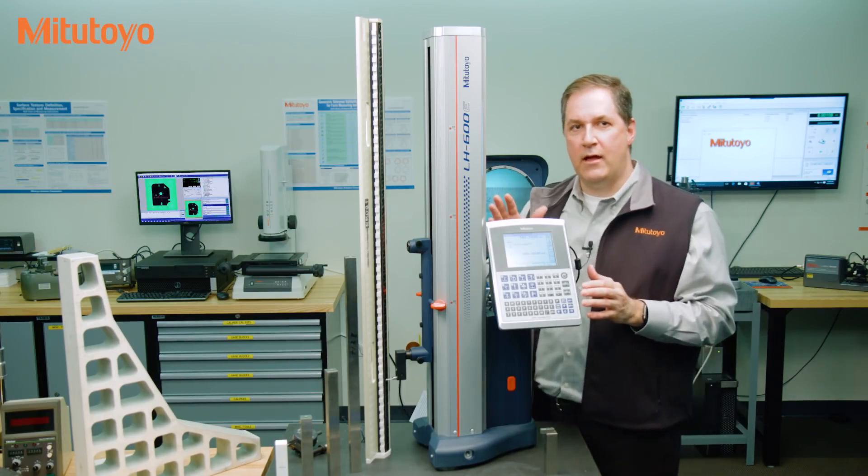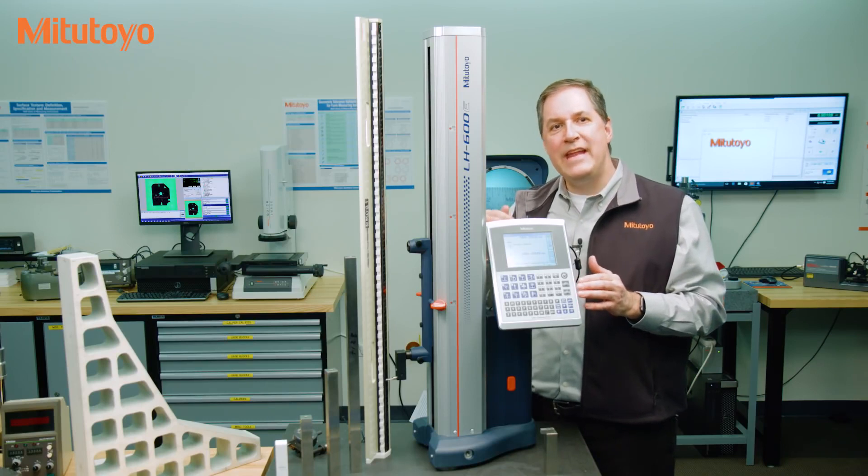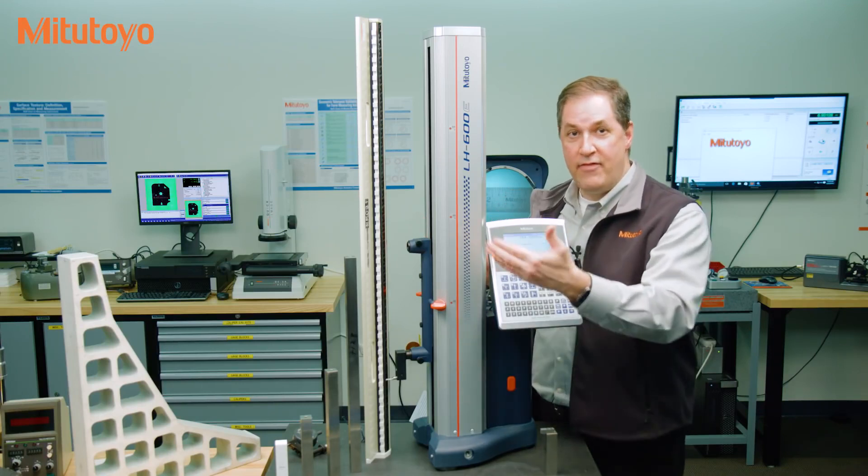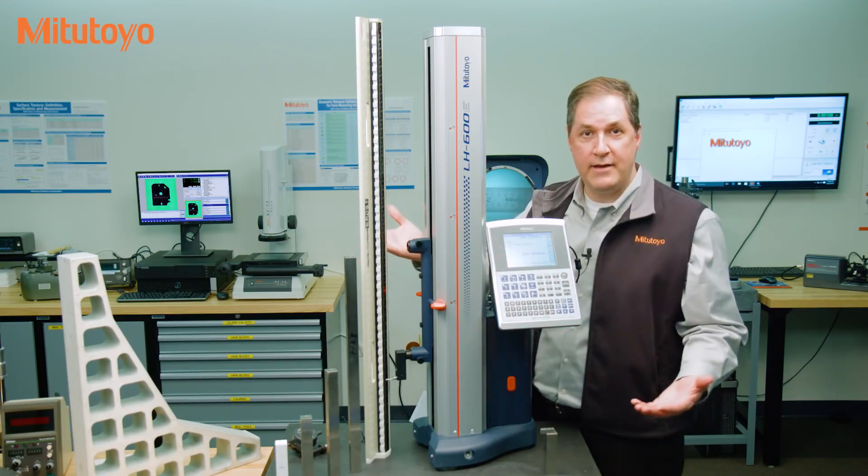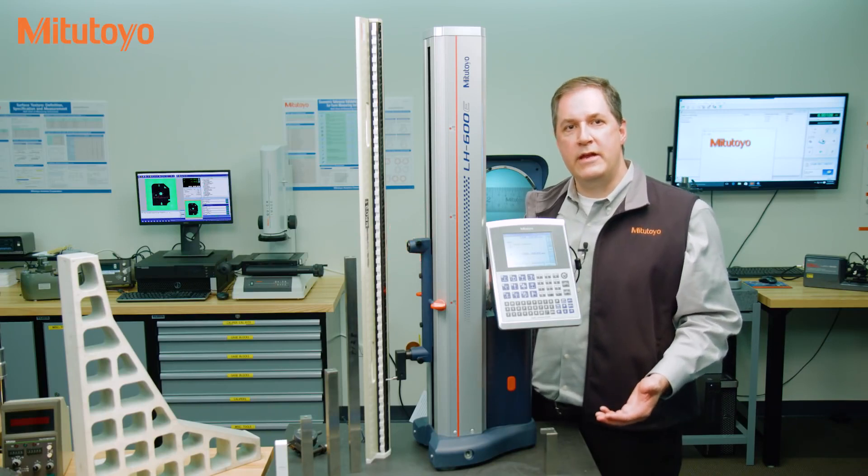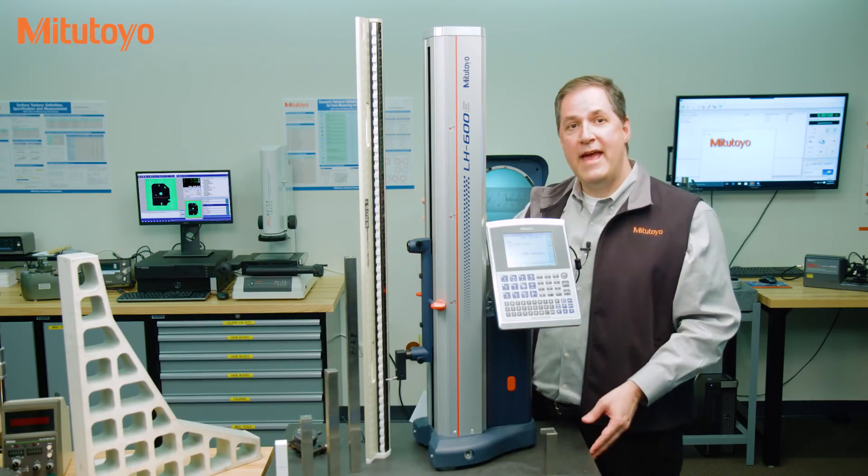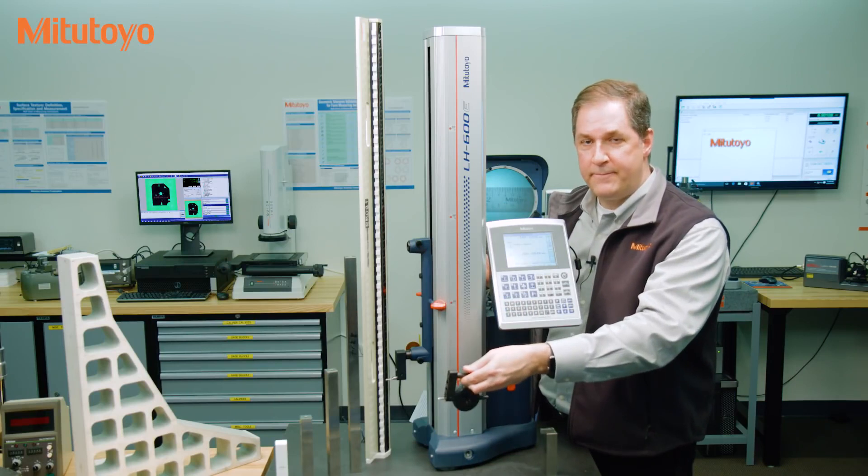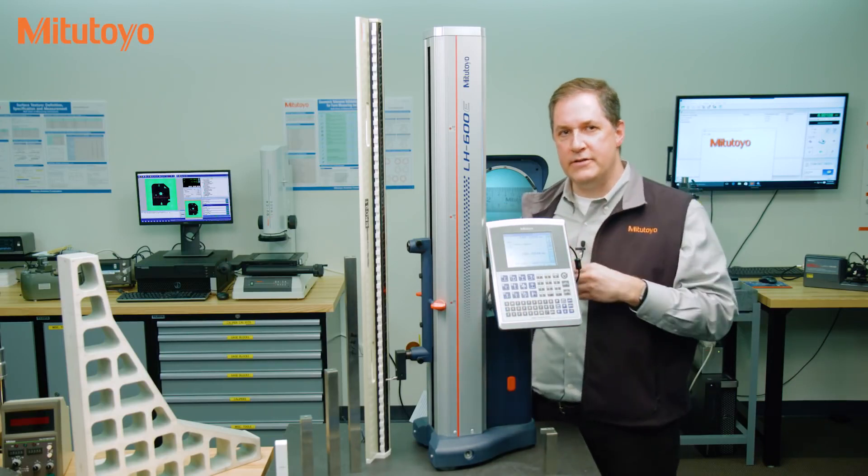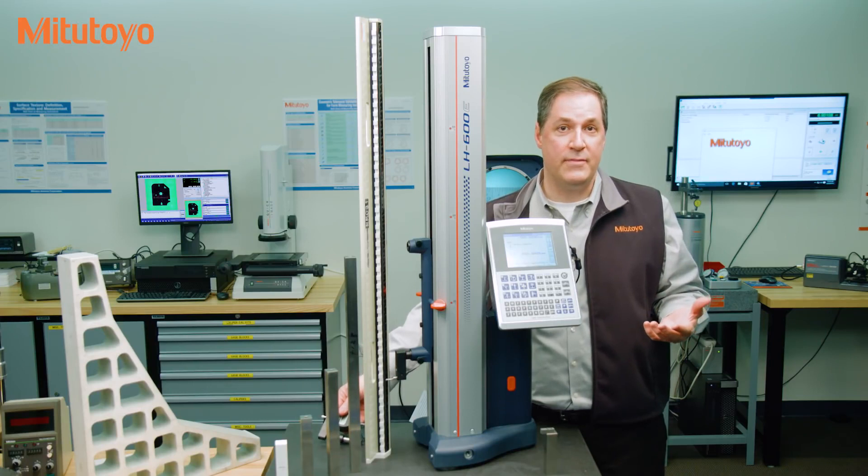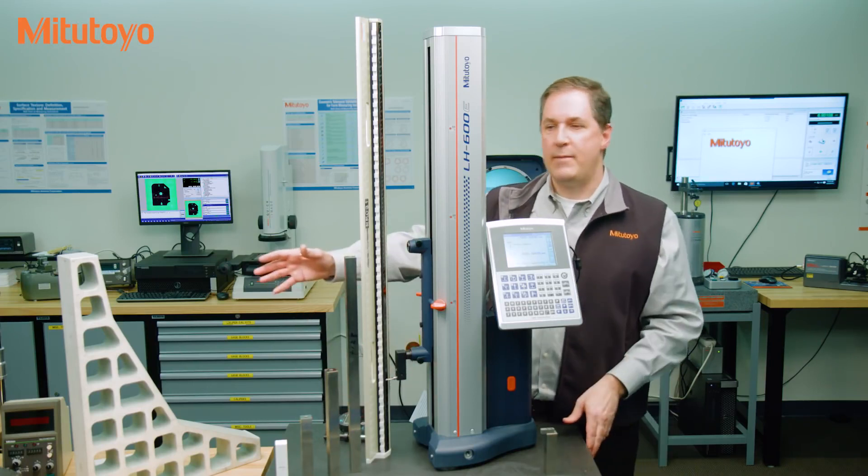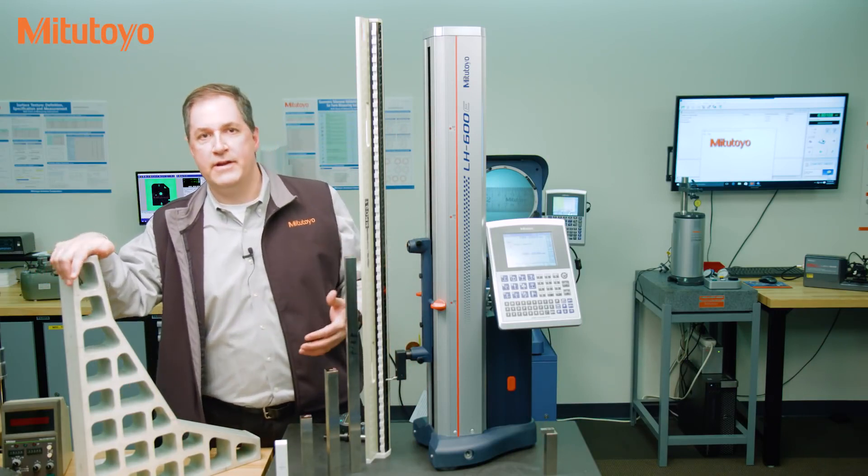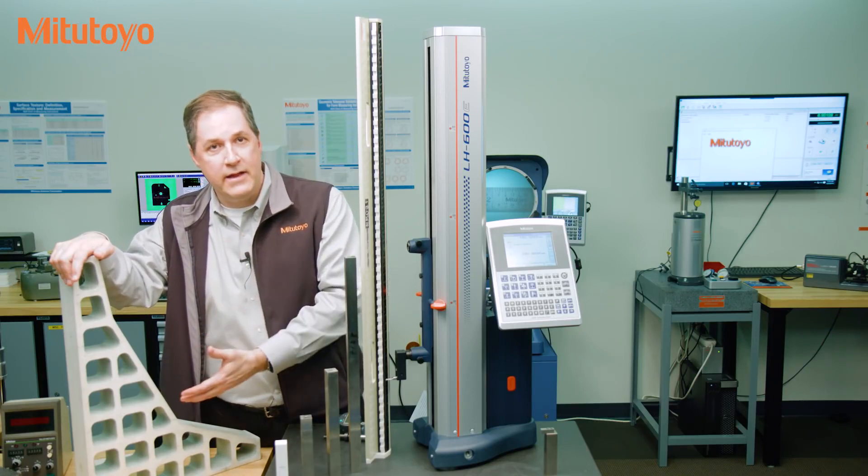Now, before we discuss the third type of calibration, what we need to talk about is what needs to get calibrated on your measuring equipment. For this linear height, if you are only measuring heights, then this test with the checkmaster for height measuring accuracy is the only thing that you need calibrated. However, this linear height has additional functions. It can measure things like straightness and perpendicularity. And if you are using these additional functions, then you need additional stuff to be calibrated. For example, we have a ceramic square over here. And if I am not using the straightness and perpendicularity functions, then I don't want to waste my money getting that calibrated.